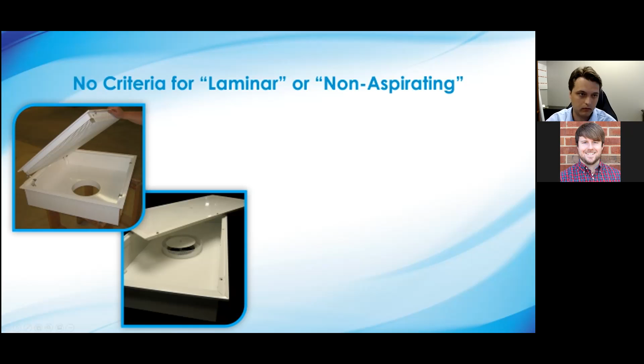And the reason that this is important is because without a good laminar flow diffuser, you can end up with aspiration, where air is actually being drawn back into the device. Dirty air is being drawn into the device, mixed with any clean air that might have been coming out of it, and that air is then delivered directly over that patient. This is actually a dirt ring on this diffuser in a hospital that we took a picture of, caused by aspiration, just like what you would see in an office diffuser, where it's mixing that dirty air and dragging it along the ceiling.